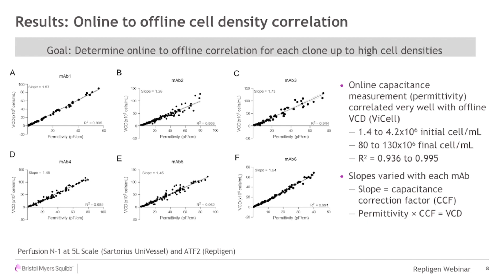We also noticed that the slopes varied for each antibody. This is a linear relationship in the N-1, and what that means is that the slope is specific to each clone. So this is something that needs to be done when you bring in a new antibody to your program: determine this online to offline correlation. We're calling this the capacitance correction factor, or CCF. Essentially, the permittivity multiplied by the capacitance correction factor is going to give you your VCD.